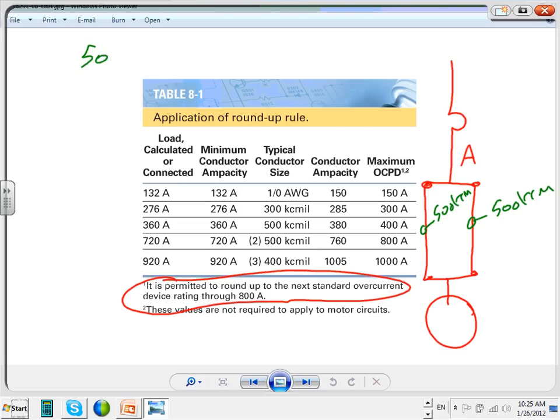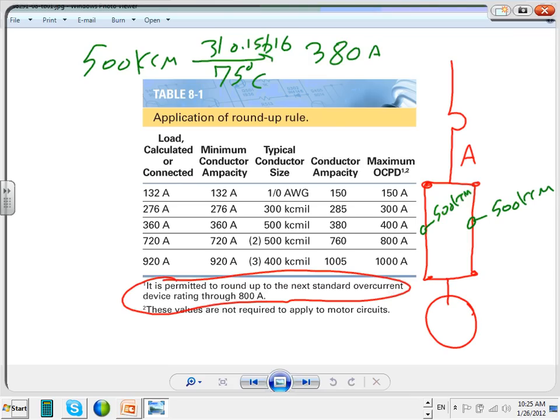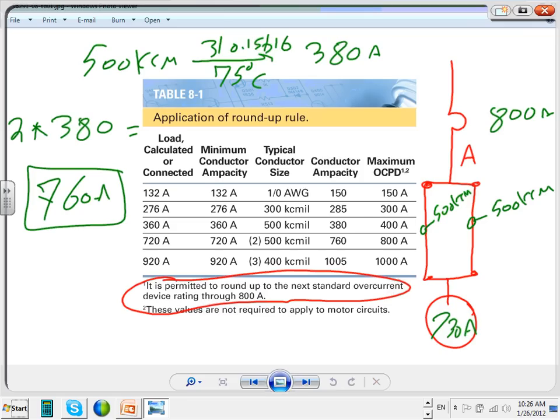If you take 500 kcm to 310.15(B)(16), it'll give you 380 amps under which column? The 75-degree column. And this is, by the way, an 800 amp load. Let's just, no, we don't want to do 800 amp. Let's make the load 730 amp. The overcurrent device is 800. So if you take 380 and multiply it by 2, because I have 2 runs, that will give you 760 amps.